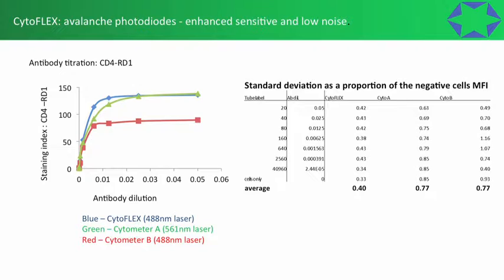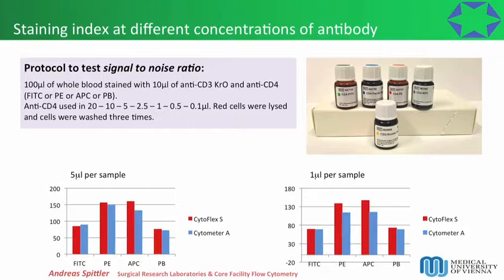This comes down to the avalanche photodiodes (APDs) in the CytoFLEX — they have very low noise. With a staining index calculation, because you divide by two times the standard deviation of the unstained, if you've got very low noise or very low standard deviation from the unstained, you're going to get a higher index value. Expressing the standard deviation as a proportion of the negative cells' median fluorescent intensity, the CytoFLEX values were all about 0.3 across the titration, whereas the other cytometers were higher. It was the low noise giving enhanced resolution and better staining index.